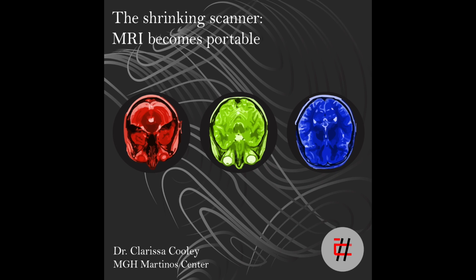So we decided we're going to make this small magnet. It's going to have an inhomogeneous field. And we decided to use that to our advantage and tailor the field variation into an image encoding field. In that sense, the image encoding field that we create with the field inhomogeneity of the magnet also allows us to eliminate some of the other electronic components, namely one of the gradient coils. And is there any disadvantage with using an inhomogeneous field compared to the homogeneous?